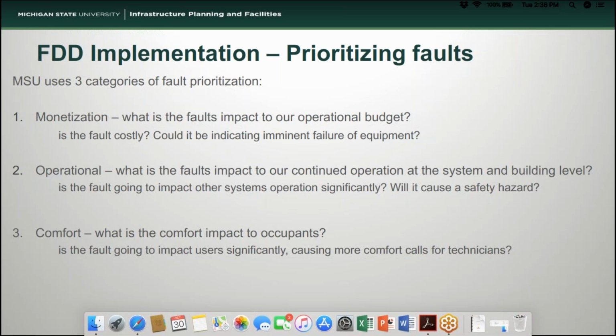And then we also classify our faults based on comfort, which is purely if this fault is not addressed, are we going to have more calls to technicians because it's too hot in the building or it's too cold in the building? Slide.